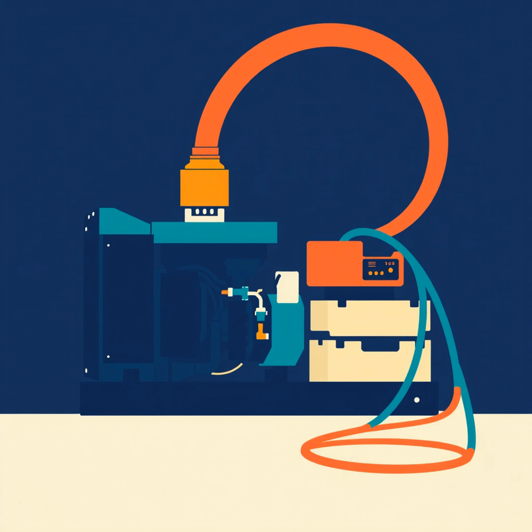The first layer is the uninterruptible power supply, or UPS. But in a high criticality facility, the UPS is not meant to run the building for hours. Its job is to bridge the gap, the black start time, between the grid failing and the generators kicking in. It handles that split second of darkness that would otherwise crash every computer, ventilator, and life support machine in the building. In a modern facility, these are often massive flywheels or lithium-ion arrays that can discharge a massive amount of energy instantly. And those generators are not just your typical backyard models you buy at the hardware store.